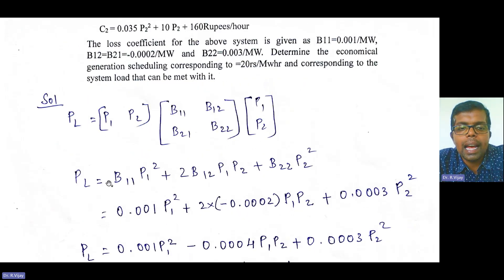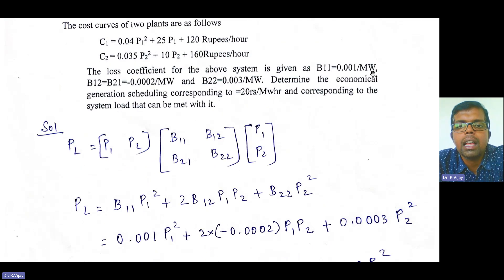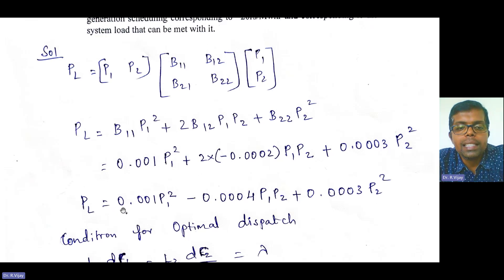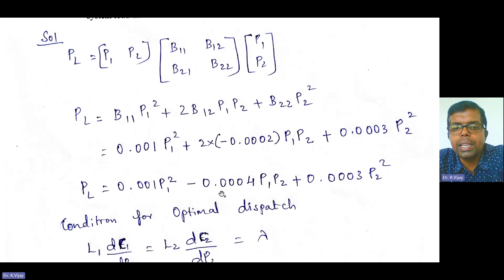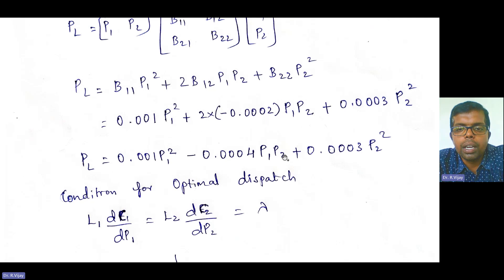After simplifying the matrix multiplication, we get: PL = B11 × P1 squared + 2 × B12 × P1 × P2 + B22 × P2 squared. Substitute the given B values carefully. Be very careful with the decimal values — do not round off. If you miss even one zero in any coefficient, the entire solution will go wrong.